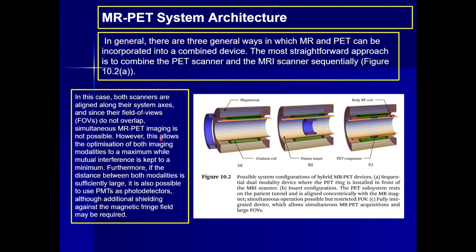However, this allows the optimization of both imaging modalities to a maximum while mutual interference is kept to a minimum. Furthermore, if the distance between both modalities is sufficiently large, it is also possible to use photomultiplier tubes as photodetectors, although additional shielding against the magnetic fringe field may be required.